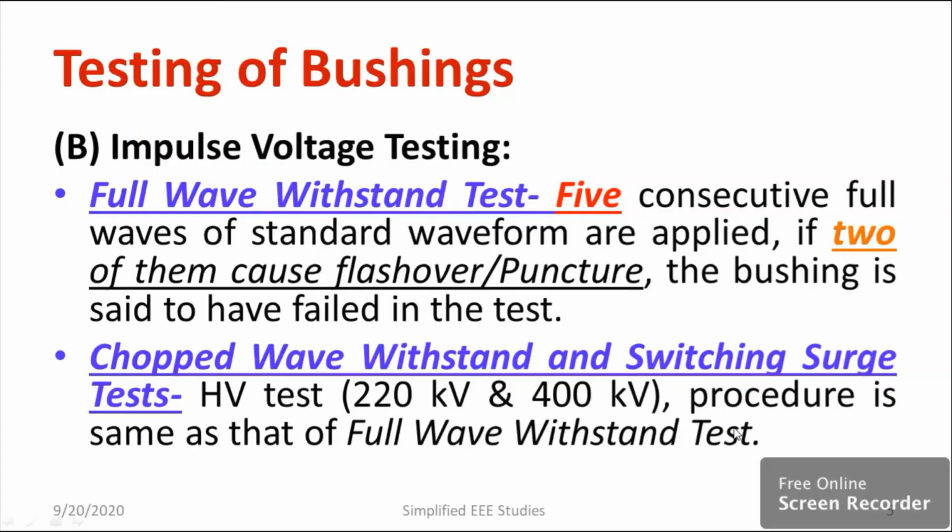Okay. The procedure is the same as the previous one. So make sure that if 2 of them cause flashover, definitely you need to reject that particular test piece. Okay, so that is regarding the full wave withstand test, chopped wave withstand test and switching surge test for bushings.